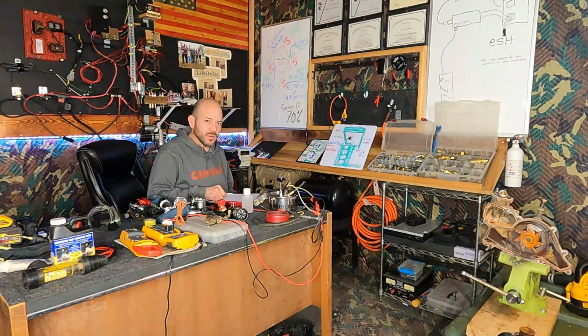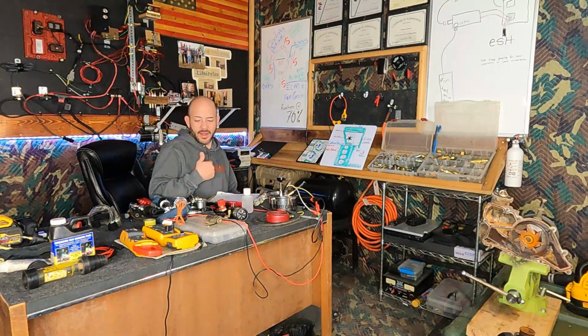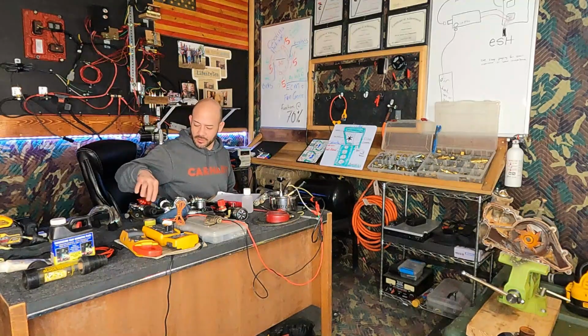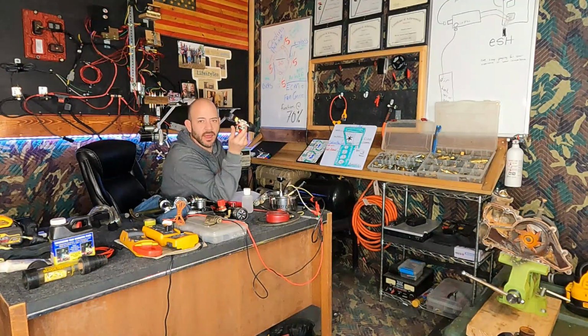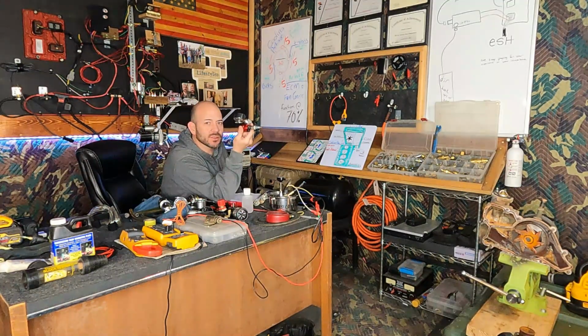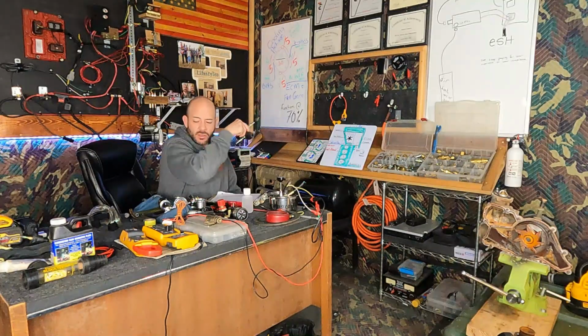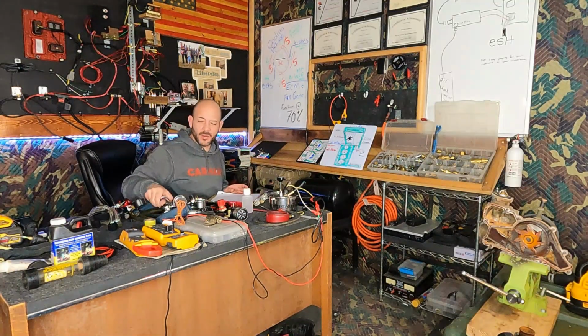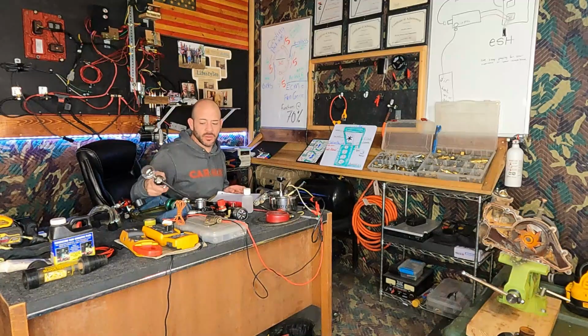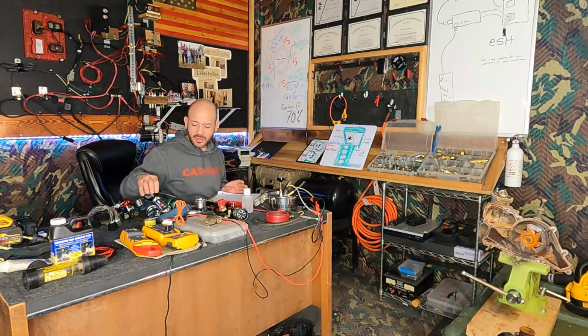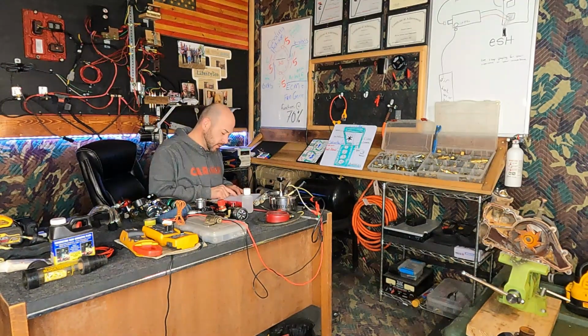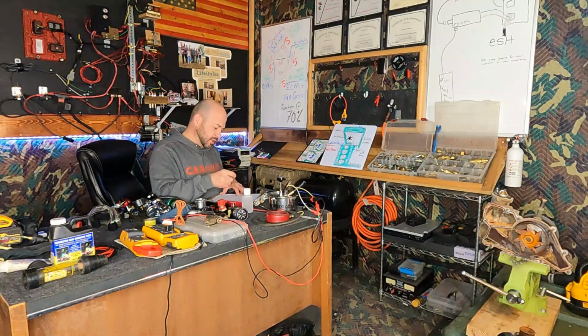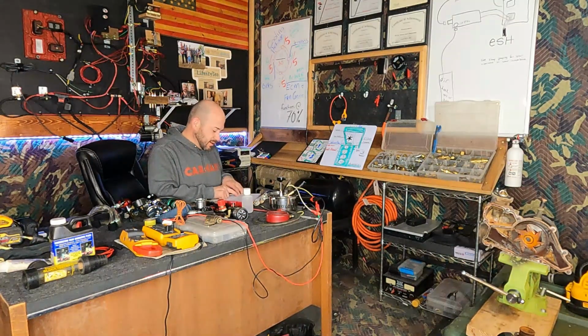They sell that through Cummins because there's a lot of coolant involved. The reason I always put coolant in under a vacuum is I let it hold the vacuum first, to make sure I don't have to redrain the coolant to make a repair or tighten a seal if something goes bad - because we always check our work. After filling it up, I'll repressurize it and make sure it holds too, but it's easier sometimes to check it before you fill it. I used to do it with air pressure and soap, but that's not necessary.